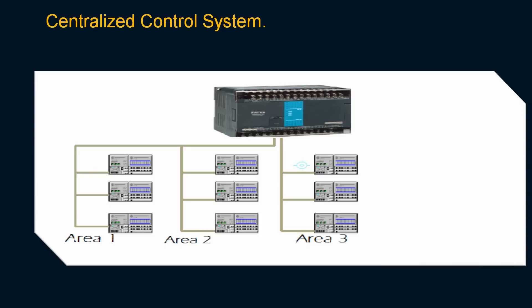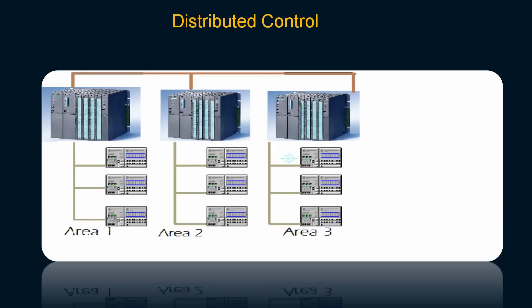To sort out that problem, we have another solution — what we call a distributed control system. In a distributed control system, we put different controllers and assign each controller to each area. Now, for example, if area 1's PLC goes down due to a CPU error or communication errors, areas 2 and 3 are still working. You have distributed your task into three different controllers, and if area 1's controller goes down, it will not affect other areas. This is the beauty of distributed control systems.